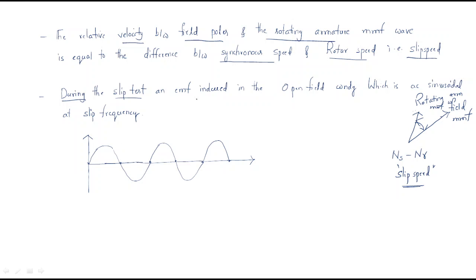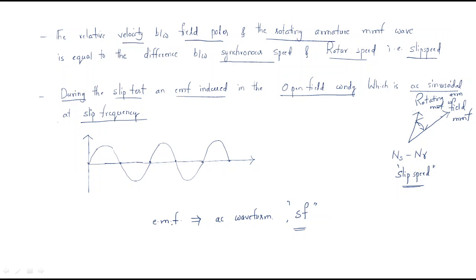During the slip test, an EMF is induced. Why is the EMF induced? Because there is a speed difference between the armature MMF and field MMF. In the open field winding, the EMF is induced, which is AC sinusoidal at slip frequency.